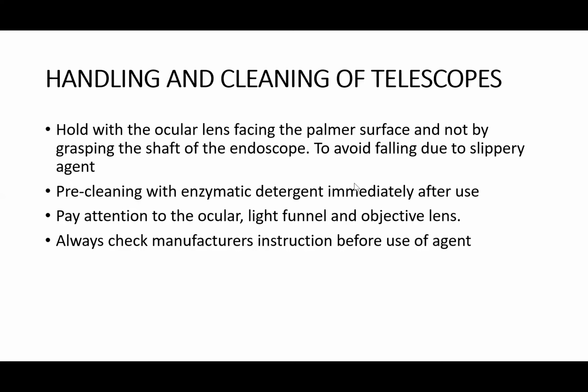Don't hold the shaft, because the shaft, you can see, is a slippery silver surface, and with the cleaning agent, it can slip off your hand. But if you hold the ocular lens on your palmar surface, you have a better grip. There you now clean properly. Do pre-cleaning with enzymatic detergent immediately after use, so that blood or tissue products don't stick to the lenses.